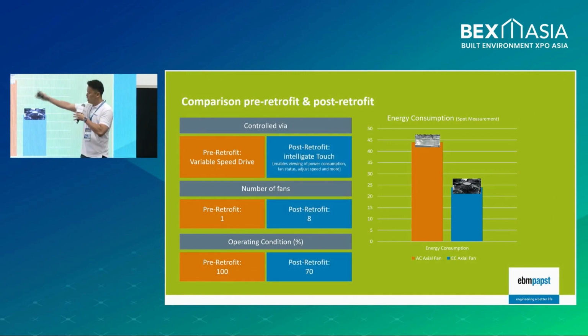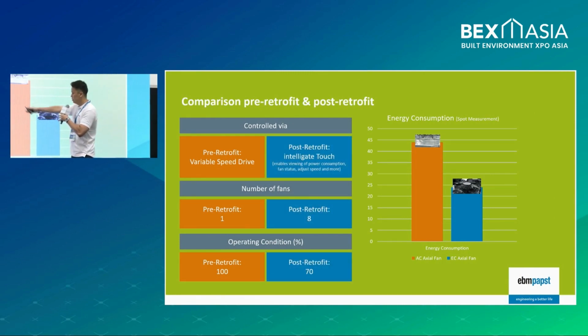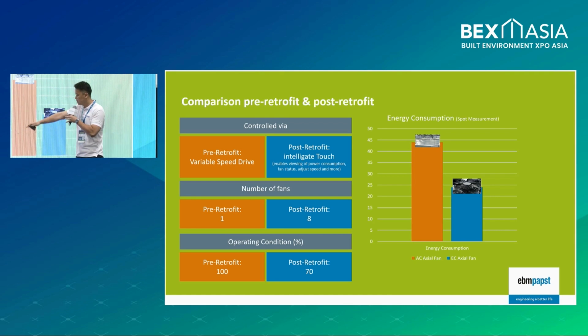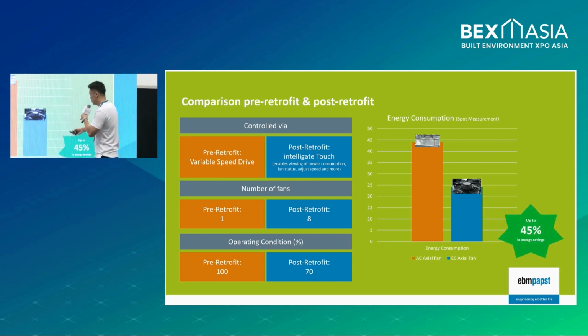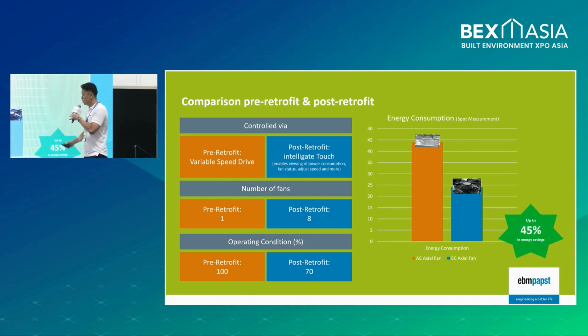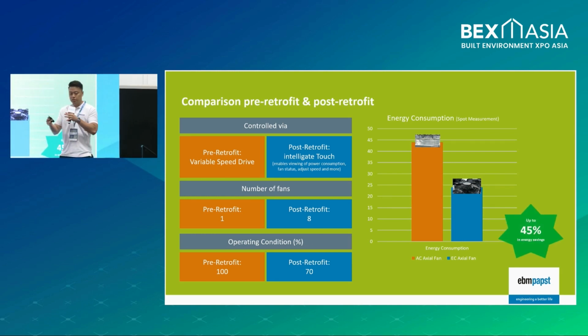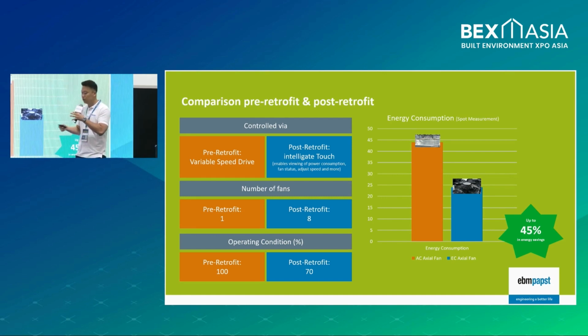So the number of fans ranges from 1 to 8, with operating condition from 100% to 70%, giving a 30% further ramp-up range. The saving is quite remarkable, about 45%. In this data center, we have retrofitted more than 50 cooling towers, so it's proven.